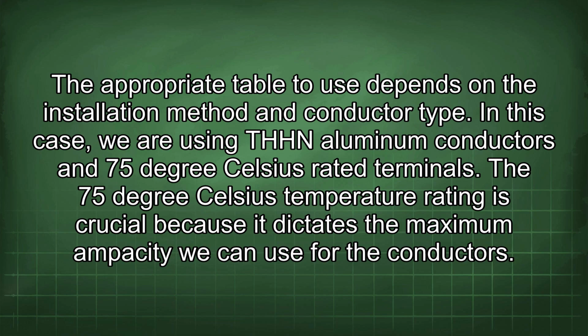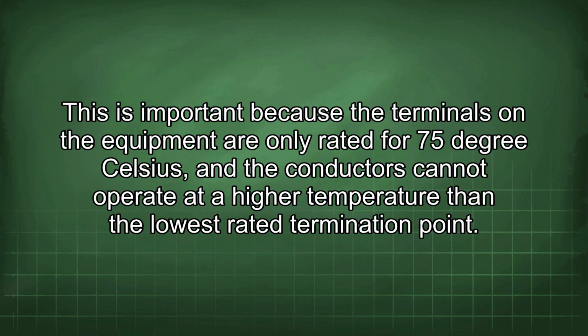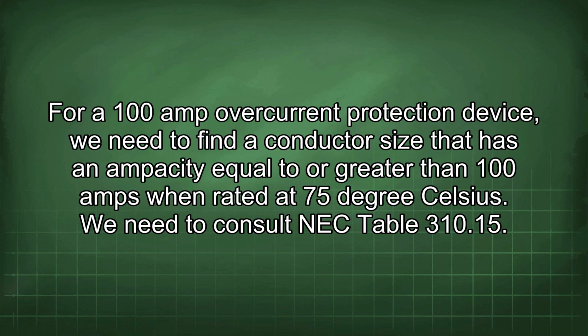In this case, we are using THHN aluminum conductors and 75 degrees Celsius rated terminals. The 75 degrees Celsius temperature rating is crucial because it dictates the maximum ampacity we can use for the conductors. This is important because the terminals on the equipment are only rated for 75 degrees Celsius, and the conductors cannot operate at a higher temperature than the lowest rated termination point. For a 100 amp overcurrent protection device, we need to find a conductor size that has an ampacity equal to or greater than 100 amps when rated at 75 degrees Celsius.